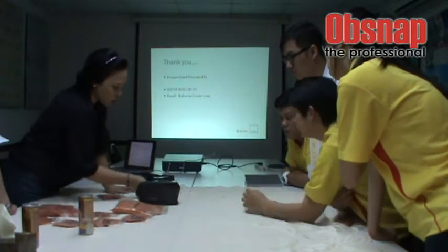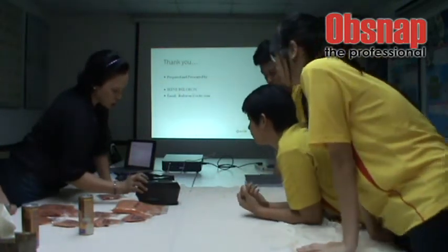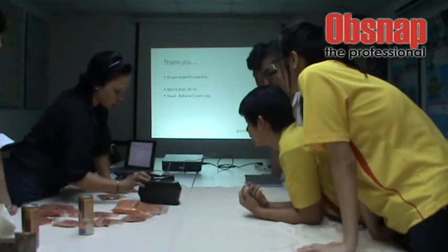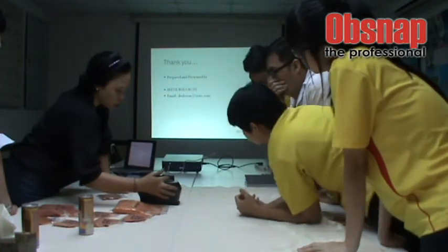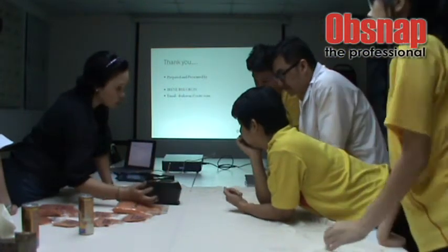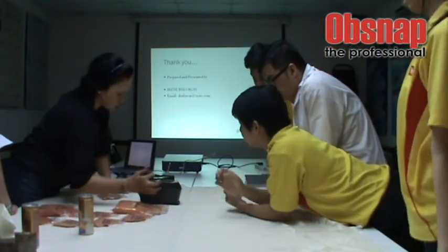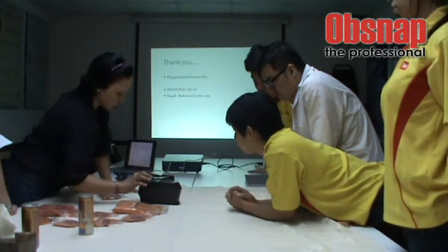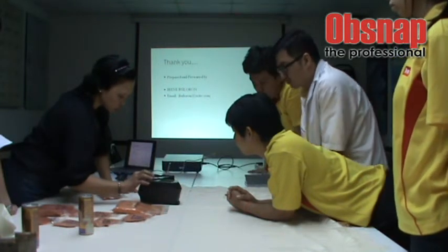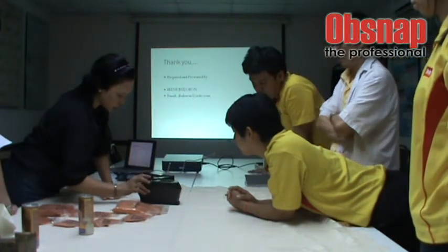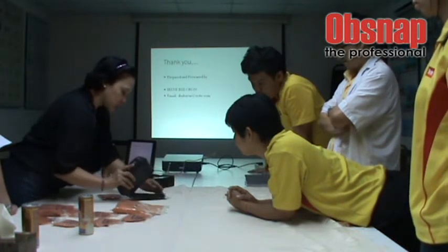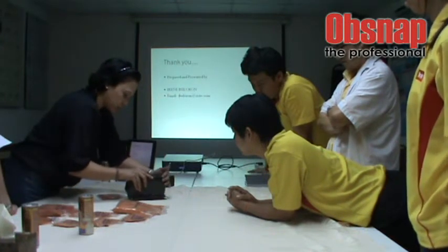Okay, so let's say I want to measure my standard. You can set up a quick compare here. With this QA, you can make a standard. You can store 1,000 standards and 4,000 samples inside this device. So I just want to do a quick compare. We go to quick compare. Okay, I'm doing the quick compare right now. Now I measure my standard, the same sample here.